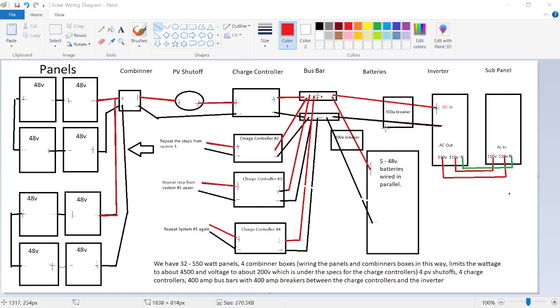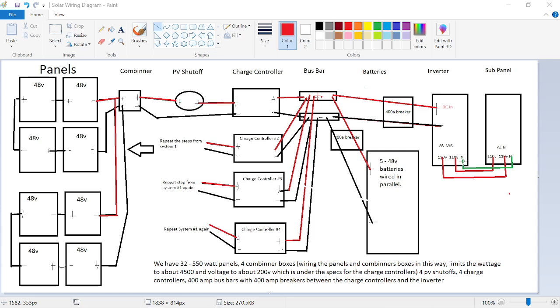So once you get through the breaker, you're into the inverter, the hot side and the cold side, DC inputs of the inverter. And then you come out of the inverter with 240 volts, so 110, 110, or 120, 120. And then the neutral that the inverter creates, you don't bring a neutral from your PG&E or your commercial power. So it comes out, it goes into my sub-panel, and that's it. But it really is, it seems like a lot of wire, a lot of stuff there. But one piece at a time, you build it one piece at a time, and it's not that tough.